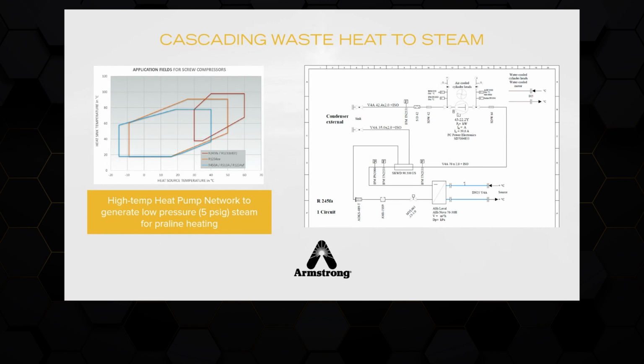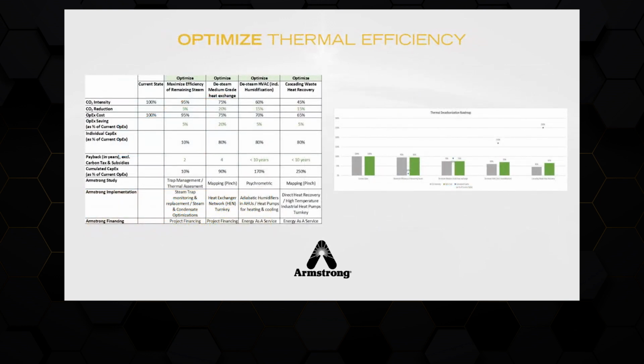What we ended up doing is, again, we designed a heat pump that could deliver steam at 10 psig, corresponding to 239 degrees Fahrenheit. The COP of this system was not as great as some of the earlier applications that we discussed, but even then, considering both heating and cooling loops, the overall efficiency was still 3 times better than a steam system. So by undertaking this optimizing step, we were able to reduce energy demand by 55%. It also helped us reduce operational expenses by 35%. All the major projects identified had a payback which was less than 10 years, which, though debatable, is exciting considering the decarbonization potential that it has.